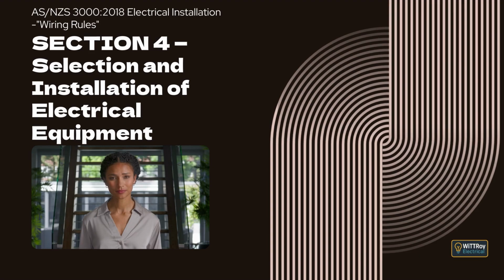It explains that where mains-powered smoke alarms are installed, they may be connected either to the lighting final subcircuit or to their own individual final subcircuit. The notes explain that connection to the lighting final subcircuit gives a clear indication that the mains supply is available, because a loss of supply would usually be noticed by the lights not operating, and it also explains that smoke alarms are not classed as safety services for the purposes of this standard. Clause 4.7 Cooking appliances. This clause introduces requirements for electrical safety related to cooking appliances.